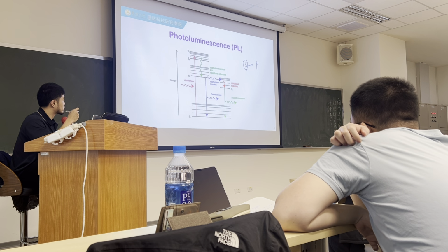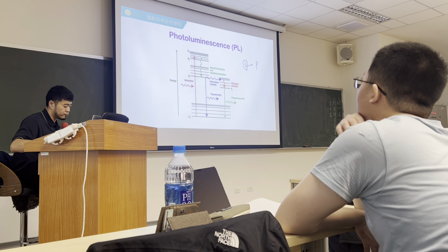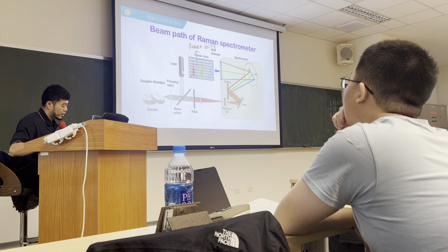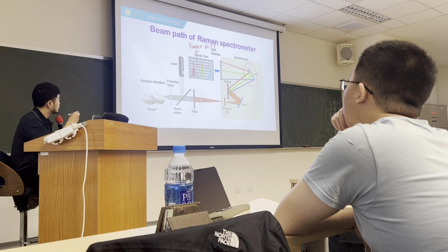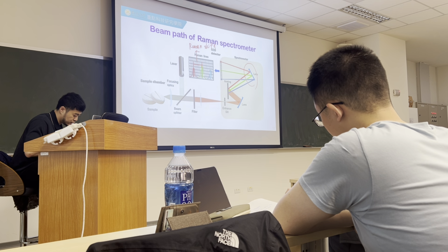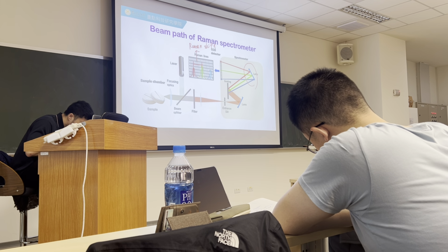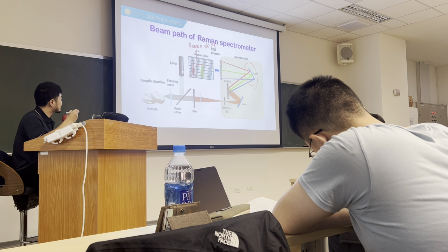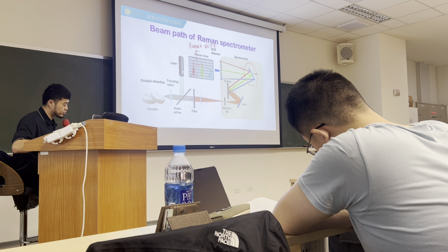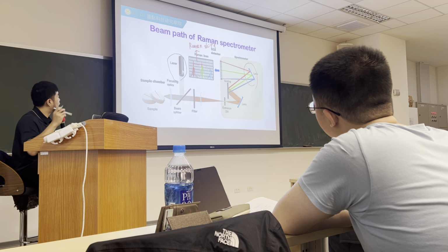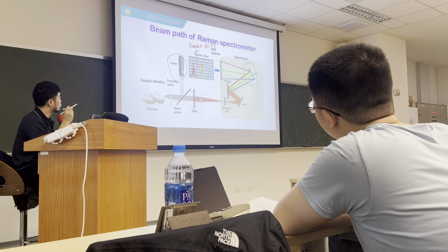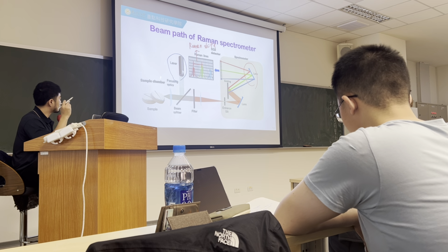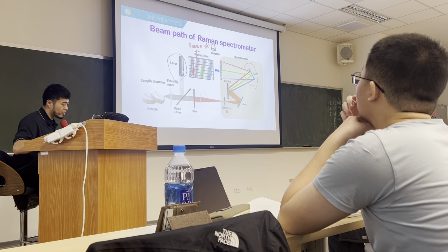In Raman spectroscopy, the most commonly seen one should be the fluorescence. In short, we are trying to observe the scattering light from your sample, but those lasers have strong excitation, and probably also excite the electron from the ground state to another electronic state. When that relaxes back, you will observe some fluorescence in your spectrum.